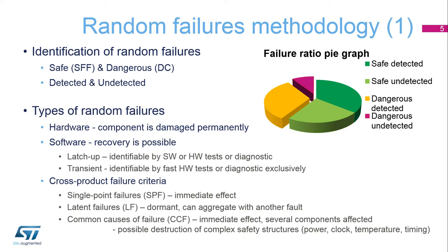The time needed to detect dangerous errors and prevent hazardous events must fit into the overall process safety time, or PST, available, which includes all the possible delays and reaction times for the system, such as on sensors or actuators. For quantification purposes, safety standards recognize a safe failure fraction and diagnostic coverage. The safe failure fraction, or SFF, is the ratio of the rate of safe failures, including the rate of detected dangerous failures, to the total failure rate. The diagnostic coverage, or DC, is the ratio of the probability of detected dangerous failures to the probability of all the dangerous failures.